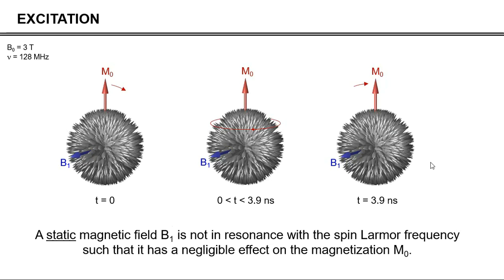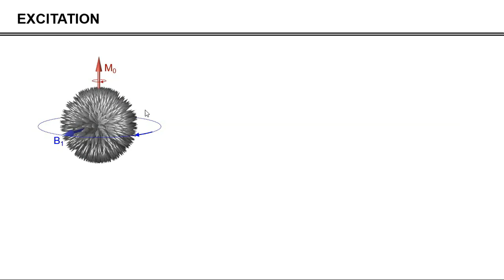In order to get a coherent rotation, the B1 magnetic field needs to have a constant phase relationship with the magnetization M0. And that can be achieved by rotating the B1 field at the same Larmor frequency as the nuclear spins. When the B1 field is rotating at the same frequency, it has a constant angle relative to M0, and therefore it has a constant torque towards rotation towards the XY plane.